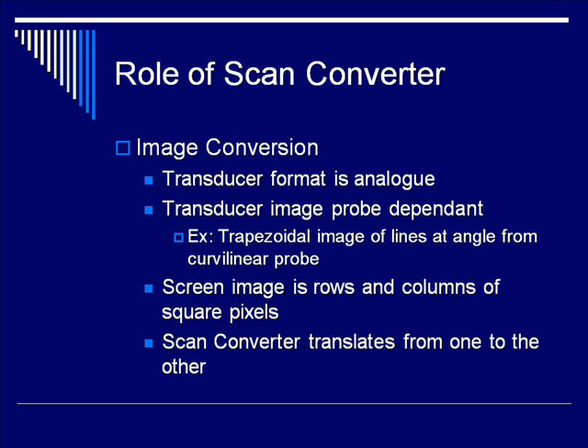Why do we need the ultrasound scan converter to change the image from the transducer's form? Remember, the transducer uses an analog form of image — varying voltages — which doesn't really display well or make things clear for us to see. Also, the size and shape of the transducer image is probe-dependent. The image for a curvilinear probe may be a weird-shaped trapezoid with large gaps between lines at the edge. The screen image you see on your display is rows and columns of square pixels, which doesn't translate well from that format. So the scan converter translates from one to the other.